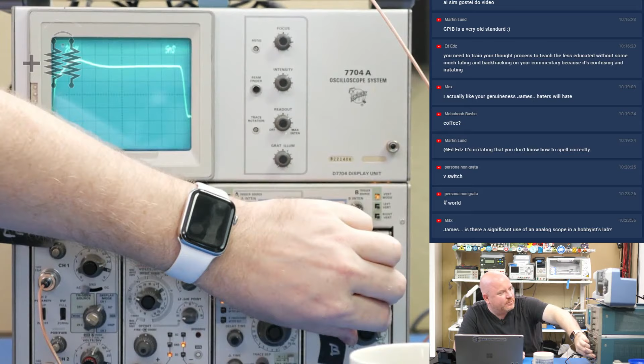What I'm actually surprised, okay, backing up, what I was actually looking for is at 50 megahertz, it stays about the same amplitude as at 10 megahertz. And that really surprises me that it's not until we get to the actual bandwidth limit that the amplitude starts to reduce. So now what I want to do is see how much reduction we can get if I keep going. So let's go to 210 megahertz. Okay, it's going down. Up to 220 megahertz. All right, 250 megahertz. Interesting.